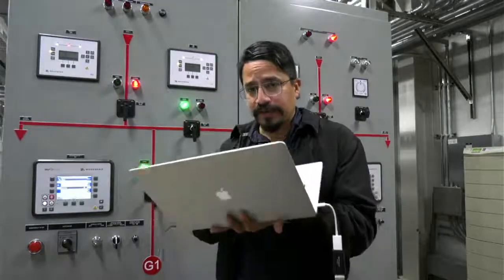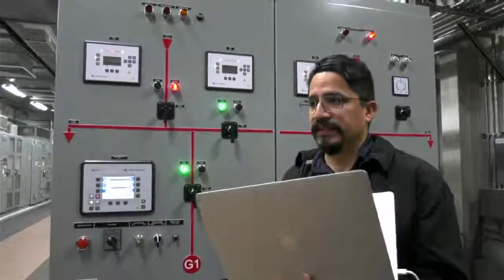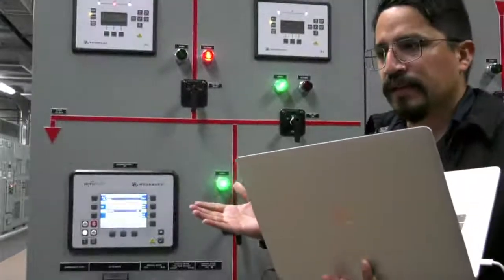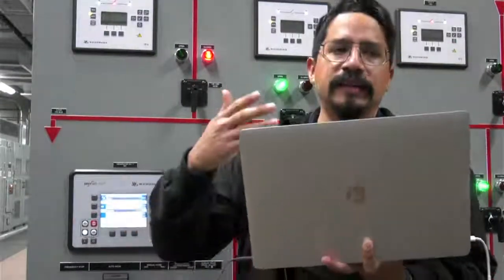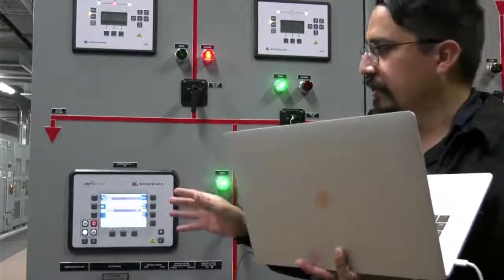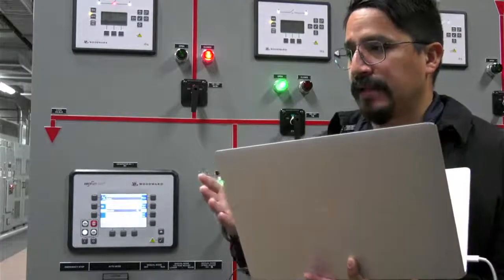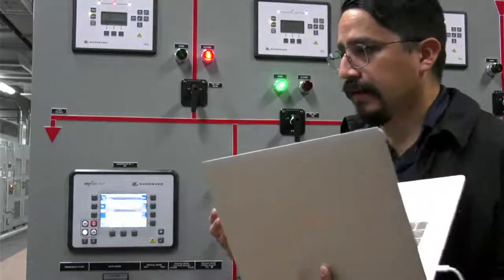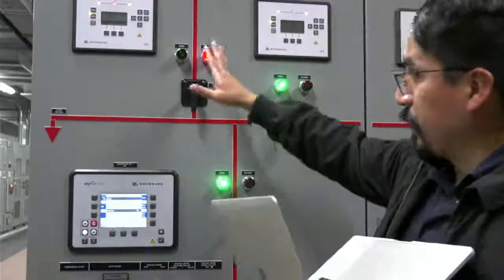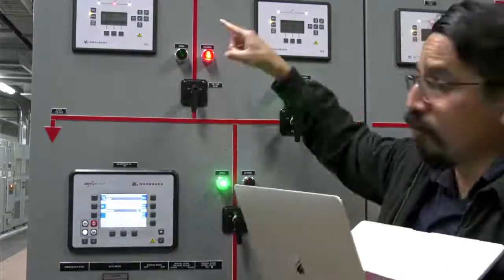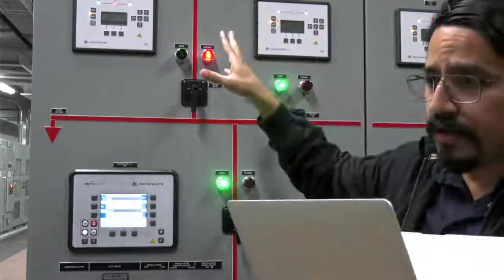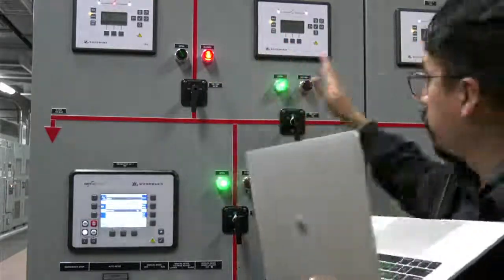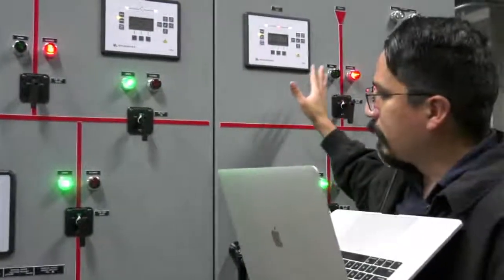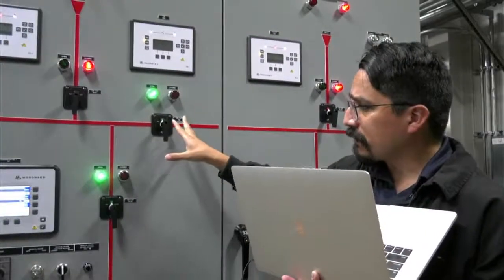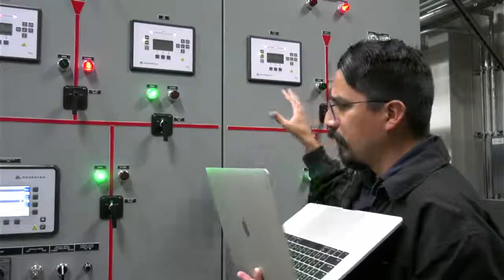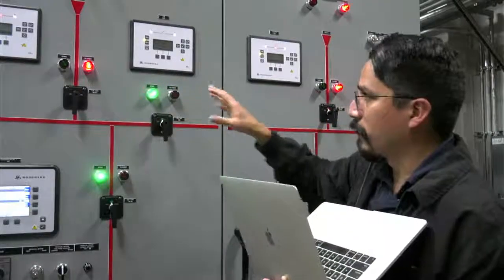So starting with the main components, they are the same as the previous cabinet, because this cabinet is a replacement of an old cabinet based on the same Woodward technology, but with new components. We also made some topology changes. Before, there was just one incoming power, one utility, the TICO, and with this new configuration you have TICO 1 and TICO 2. We also included a tiebreaker in the middle, so you have options to back up the power from either TICO 1 or TICO 2.